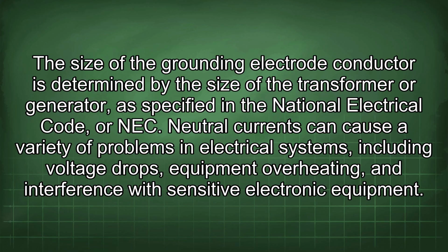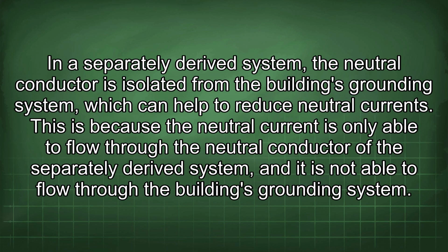Neutral currents can cause a variety of problems in electrical systems, including voltage drops, equipment overheating, and interference with sensitive electronic equipment. In a separately derived system, the neutral conductor is isolated from the building's grounding system, which can help to reduce neutral currents. This is because the neutral current is only able to flow through the neutral conductor of the separately derived system, and it is not able to flow through the building's grounding system.